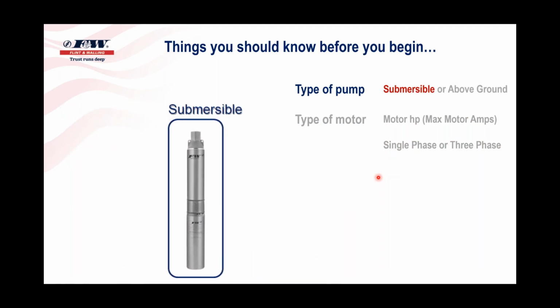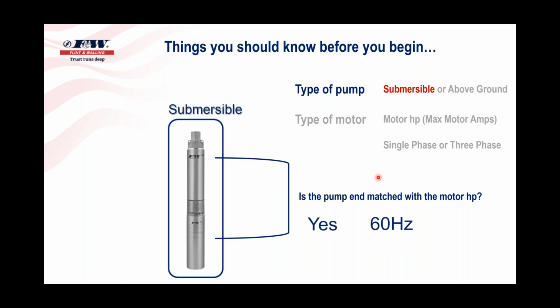So for example, if we choose a submersible pump, there's a couple other things that we ought to know about. By and large, first and foremost, we need to know if the pump end is matched up with the motor horsepower. If you're going to take this drive out and put it on the off-the-shelf Flint & Walling pump or somebody else's brand of pump, meaning you buy a 1.5-horse pump and you get a 1.5-horse pump and motor, if those are matched, then we're going to set the max frequency at 60 hertz. Any above ground pump, should we have selected a centrifugal pump, will always run at 60 hertz.